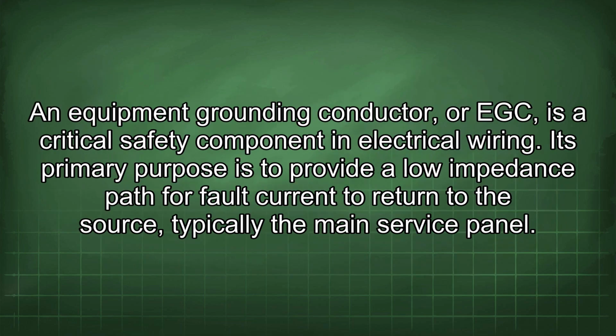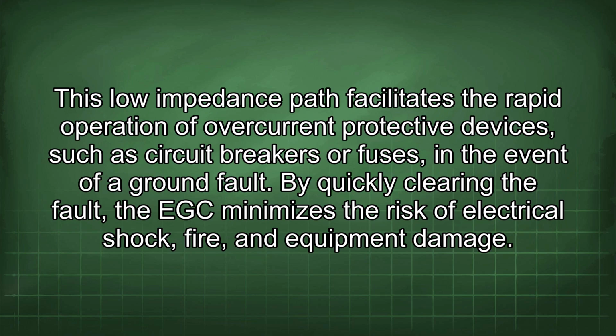Now let's talk about some details about the equipment grounding conductor. An equipment grounding conductor, or EGC, is a critical safety component in electrical wiring. Its primary purpose is to provide a low impedance path for fault current to return to the source, typically the main service panel. This low impedance path facilitates the rapid operation of overcurrent protective devices such as circuit breakers or fuses in the event of a ground fault. By quickly clearing the fault, the EGC minimizes the risk of electrical shock, fire, and equipment damage.